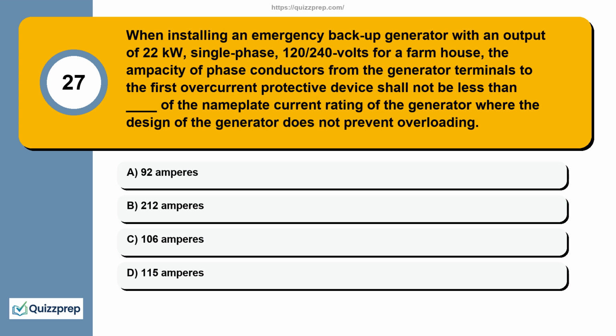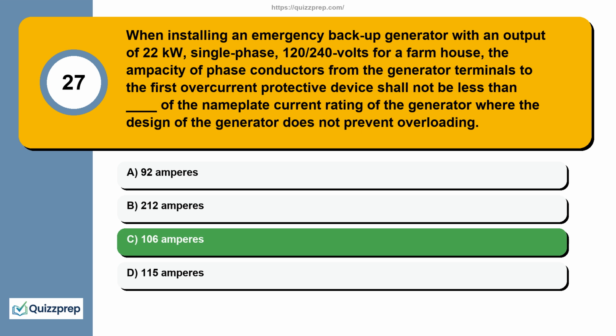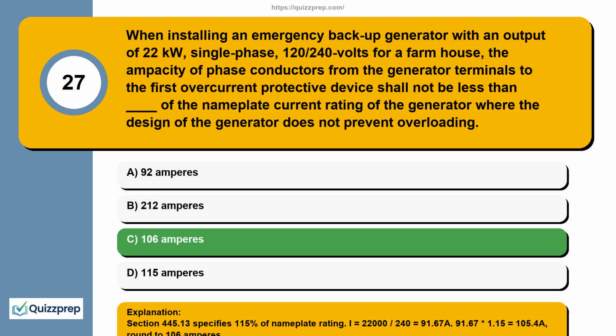Question 27. When installing an emergency backup generator with an output of 22 kilowatts, single phase, 120/240 volts for a farmhouse, the ampacity of phase conductors from the generator terminals to the first overcurrent protective device shall not be less than blank percent of the nameplate current rating of the generator where the design of the generator does not prevent overloading: 92 amperes, 212 amperes, 106 amperes, 115 amperes. Section 445.13 specifies 115% of nameplate rating. I equals 22,000 divided by 240 equals 91.67 A; 91.67 times 1.15 equals 105.4 A, round to 106 amperes.